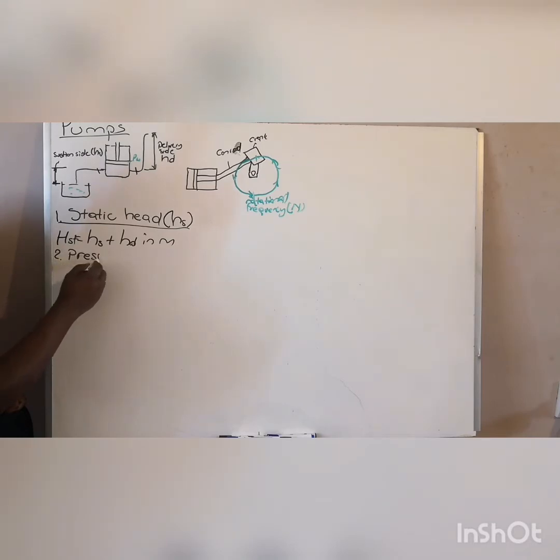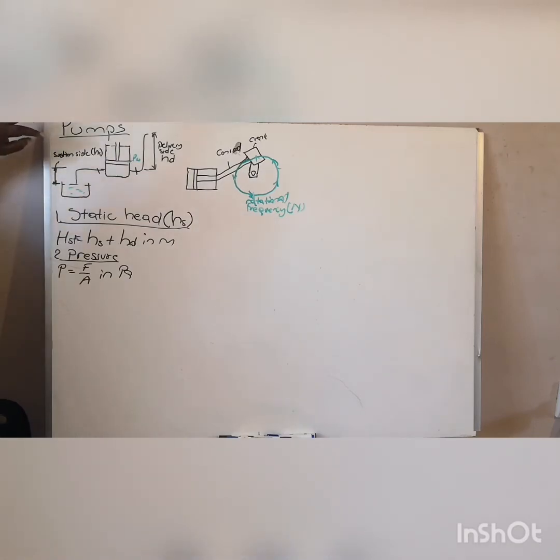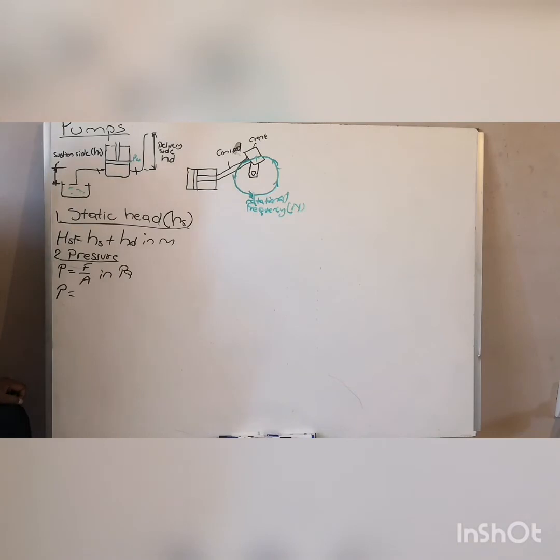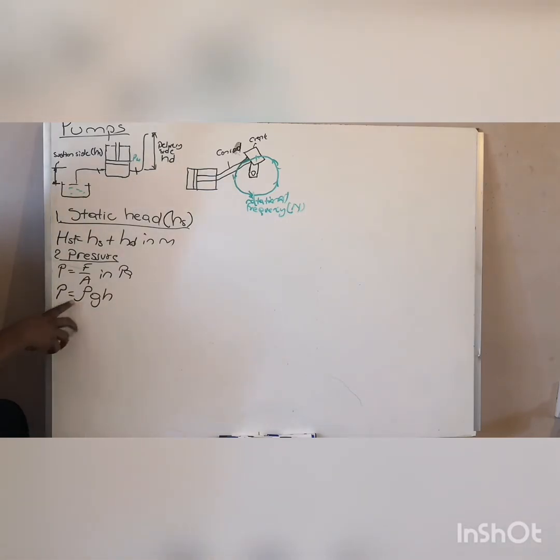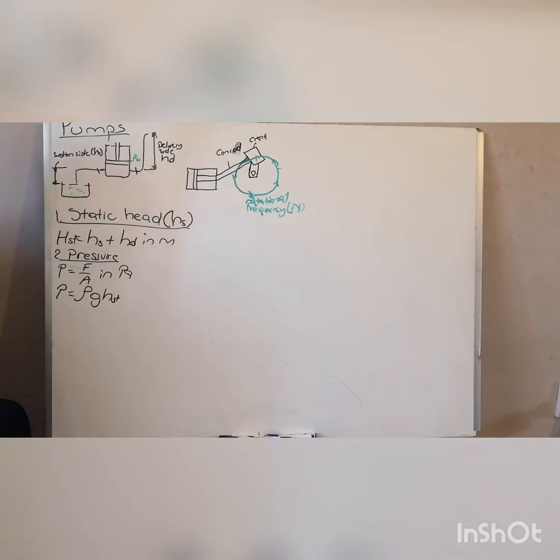The second formula is pressure equals force over area, in Pascals or kilopascals. This equation is applicable when you have a force exerted by the piston. If you don't have a force from the piston, the equation you will often use is P equals rho·g·h, where rho is density, g is gravitational acceleration, and h is your static head. This gives you the pressure delivered.